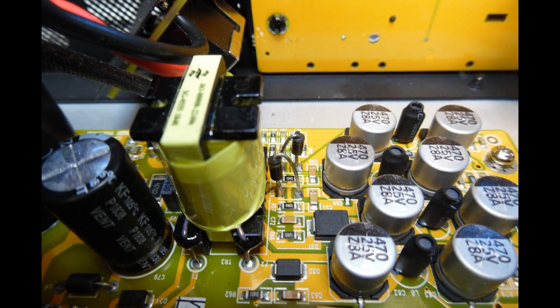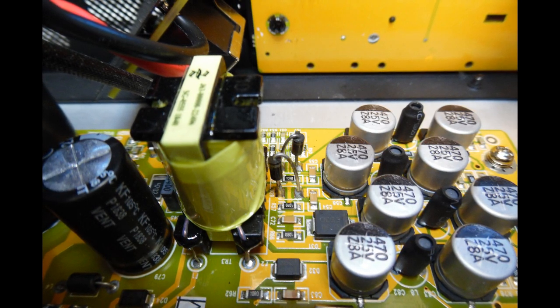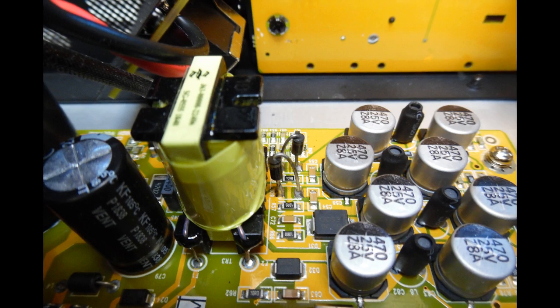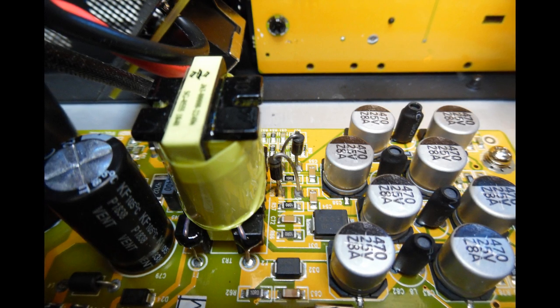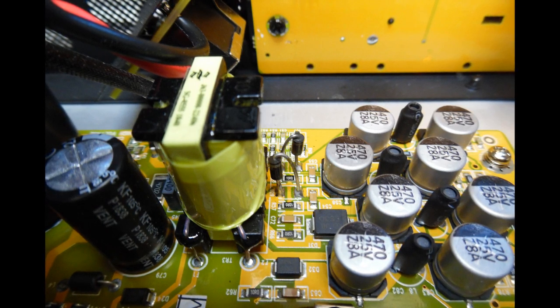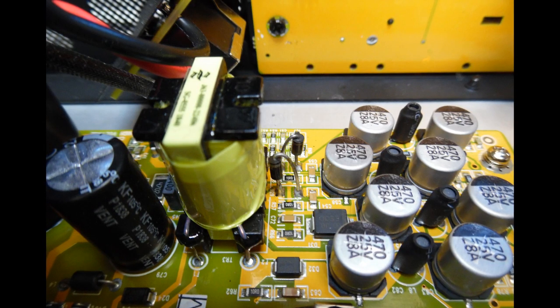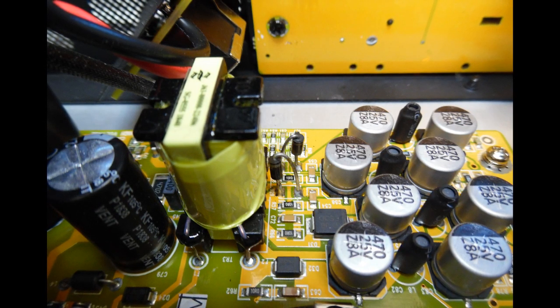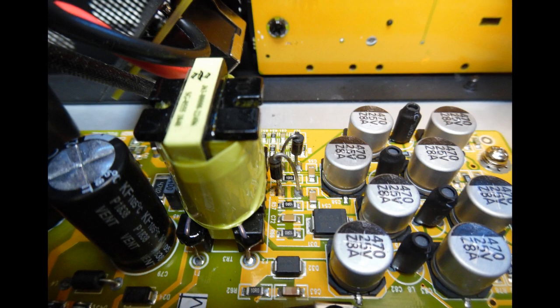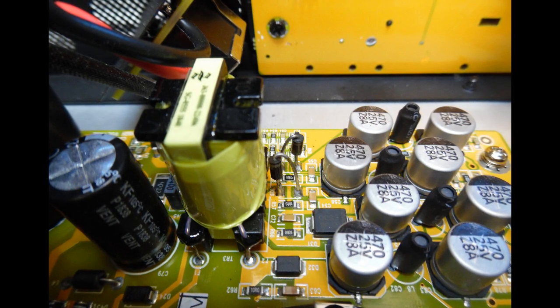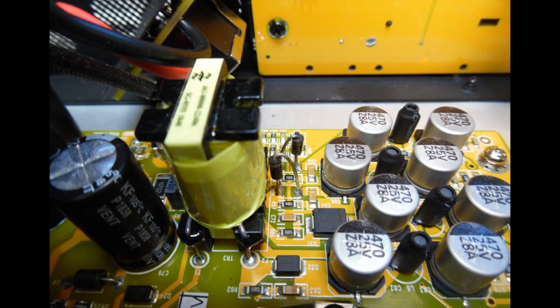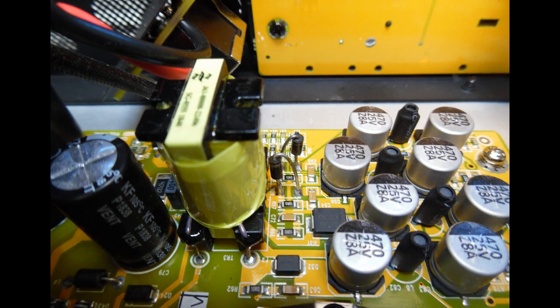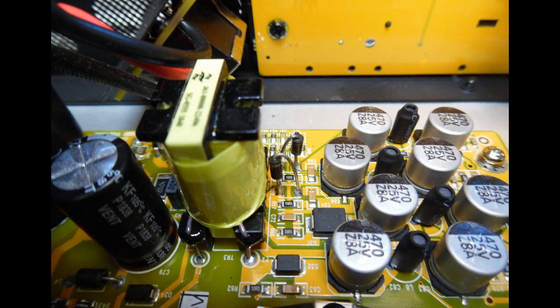It discharges via a resistor down to ground, and then we measure across the capacitor just to make sure it's fully discharged. Or you can buy capacitor discharge devices, which can be a bench mount type device, or more commonly they're almost like a pincer with an LED, and when the LED goes out, it indicates the capacitor no longer holds charge.